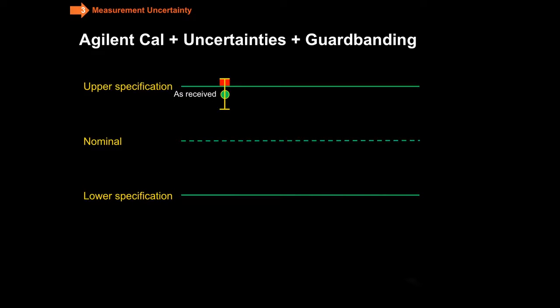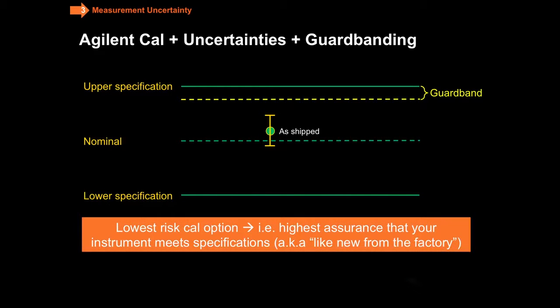Some of our customers tell us that they cannot afford risk. And so what we then do with guard banding is we take that same expanded measurement uncertainty and then we establish on the yellow dotted line a tighter acceptance limit. Then we readjust and what we end up with after adjusting is a measurement result like this.